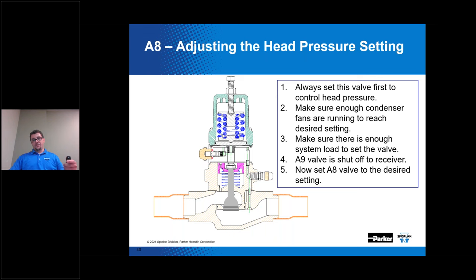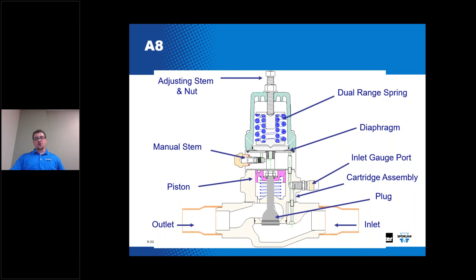Regarding rebuilding or servicing the A8: note the location of the gauge port. Years ago we relocated the gauge port from the cartridge assembly to the valve body. If you're ever replacing the cartridge on an old A8, you'll lose your gauge port because the new cartridge assembly doesn't contain one. Be aware that you'll need to install your own pressure tap in order to get the valve set after replacing that cartridge assembly.